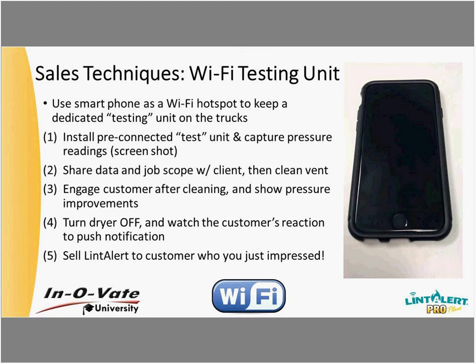What I actually do is keep a LintAlert on my service truck and connect it to my personal phone's Wi-Fi. When I get to a new customer's job, I turn on my mobile hotspot so my Wi-Fi is broadcasting, and I take my already-connected LintAlert and plug it in, tapping it into the customer's dryer duct system. By tapping into that dryer duct, I open my phone and I'm already capturing real-time readings of what's going on in that customer's home. While this is happening, I discuss with them the back pressure readings I'm seeing and go over the visual information, like whether it went through the roof or the wall vent, what the transition duct looks like, or if there's a lot of lint behind the system.